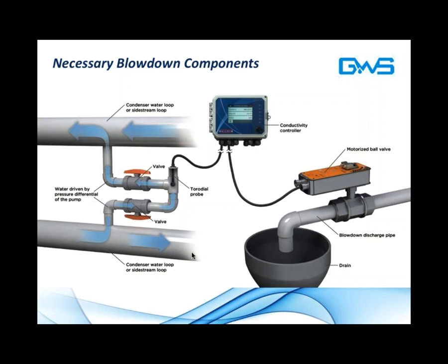A component that's necessary in all cooling systems, as you may know, is a functional blowdown system, which includes a conductivity controller. In this case, it includes a toroidal probe, which passes electricity through the water. Based on the conductivity, the amount of electricity returned, it can calculate the amount of dissolved solids in the water. When those dissolved solids reach a certain threshold due to evaporation in the cooling tower, the conductivity controller signals the motorized ball valve to open, and bulk water is blown down the drain, forcing the cooling tower to add new makeup water, which is coming in at a much softer level.